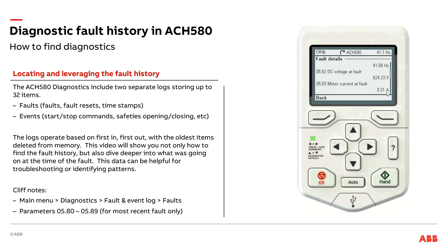I can see what the load of the drive was — my little demo case motor was only at 0.21 amps. Same thing with torque, only at three and a half percent because it's just a little demo. But in a traditional application, if I had an issue on the load side, maybe a bearing going out or something mechanical going on, you might see that current being a lot higher compared to the drive rating or the torque being a lot higher than it typically would be. So amps and torque will give you good guidance if there's a problem on the output side of the drive.